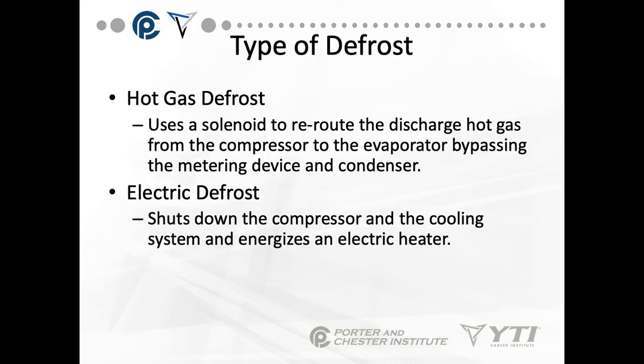We have two different types of defrost. We have hot gas defrost, which uses a solenoid to reroute the discharge hot gas from the compressor to the evaporator, bypassing the metering device and the condenser. We take our very hot discharge gas — coming off the compressor we have a high pressure, high temperature vapor — and we route that around the metering device and the condenser to keep it hot. We bypass the entire liquid line and dump it right into the evaporator, which causes a very high temperature gas in that evaporator, and it actually melts any ice off of it.